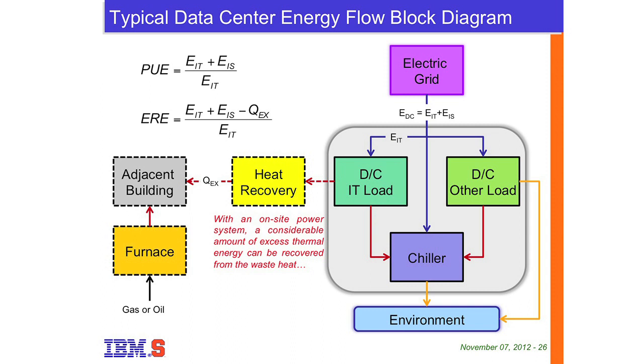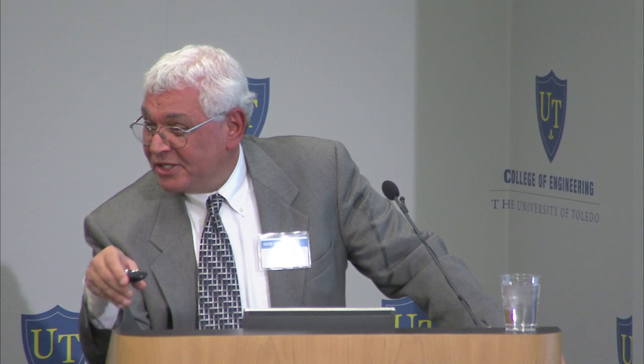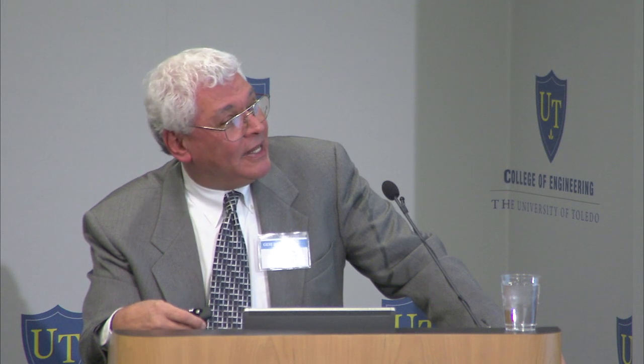So if I were to take the waste heat from this data center, whether it has a cogeneration system or a conventional system, and send it to a greenhouse next door, then that amount Q exported, they subtract it from the numerator of what would have been the PUE, but they don't define it as PUE prime or PUE2. They define it as energy reuse effectiveness. So it's possible in this case to end up with EREs that are less than 1. But it does not mean that the PUE is less than 1, it just means that the ERE is less than 1.